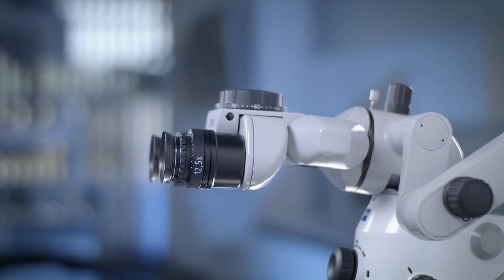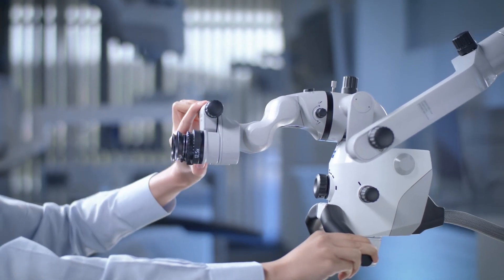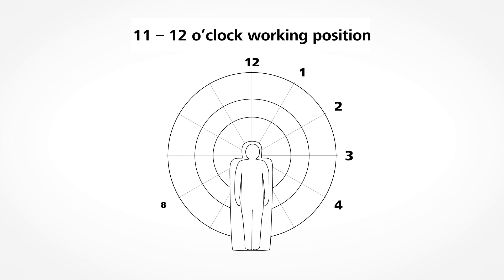Compared to the tiltable tube, the foldable tube adds an additional 4 cm in the extended setup. This could be an advantage if you work in 12 o'clock working position a lot and need more distance from the patient.